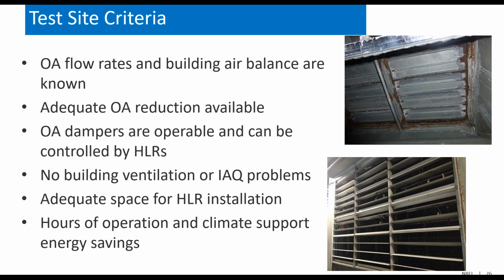And you need to make sure that when you close down those outside air dampers, you're not closing them completely. Because you still have to have some ventilation to balance your building with the exhaust in your building. So you want to make sure you're still maintaining a positive pressure in the building. And obviously, you want to make sure there's enough room for the HLR installation, which usually is not a problem. And then really, climate and hours of operation to achieve those energy savings, and we'll talk more about that in a moment.